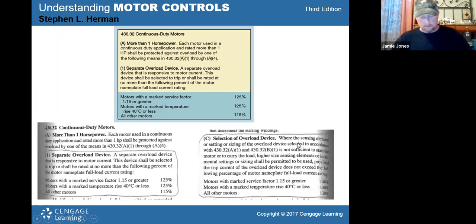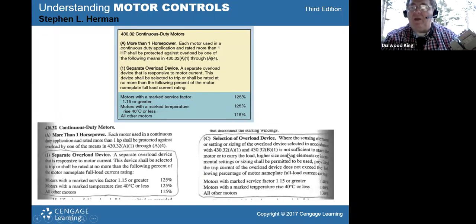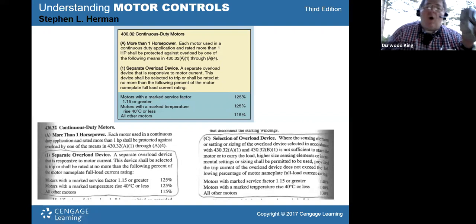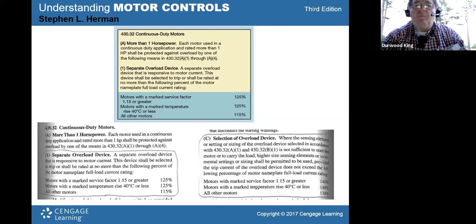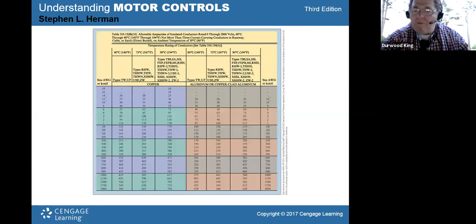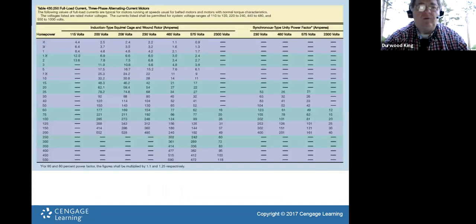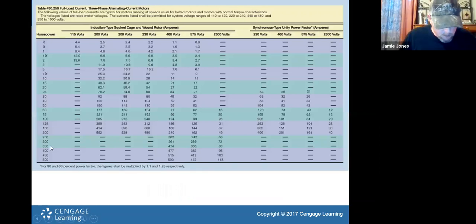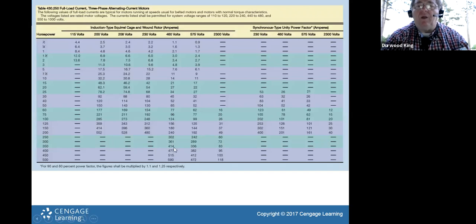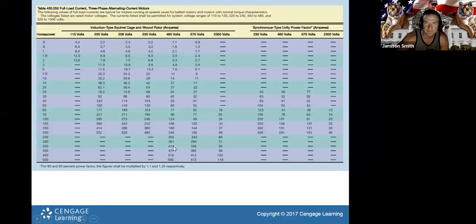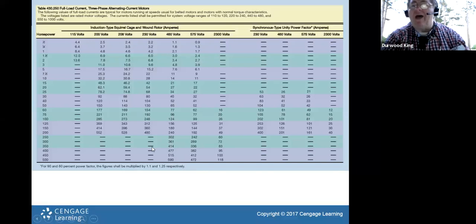It says here that where your sensing element or overload size is not sufficient to start that load, a higher size is actually allowed as long as you don't go above 140%. All right, so what would it be for the motor we just looked at? What was the original number on the amps? The original nameplate number that we looked at. It was a 414. You go back to that number there, that 414, and you multiply that by 140%.